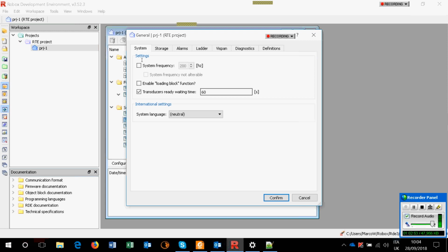So, according to the machine, according to the system, you may have a bigger time. Mainly 1 minute, which is set as default, is good, for example, for Siemens motors. They are very nice, very performing, but very slow to be switched on. Many times having 1 minute of time to wait is very good to enable a good communication from the controller to the motor and vice versa.